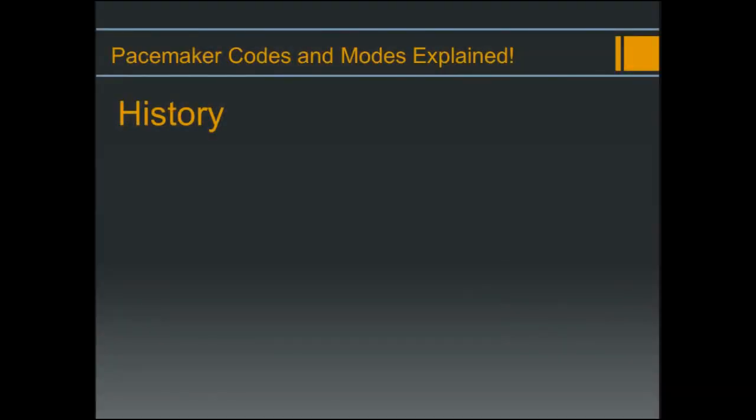In order to explain pacemaker codes and modes and where they came from, we need to take a little look at the history of pacemakers. In the early days, pacemakers really weren't all that complex — you would set the rate, implant the device, and were unable to change that rate. As pacemakers became more complex, capable of being reprogrammed and pacing and sensing in multiple chambers, a problem arose: different companies and physicians were using different terms to explain how that pacemaker was programmed to function. In 1974, the Intersociety Commission for Heart Disease Resources recommended a three-letter code to help simplify and standardize terminology.